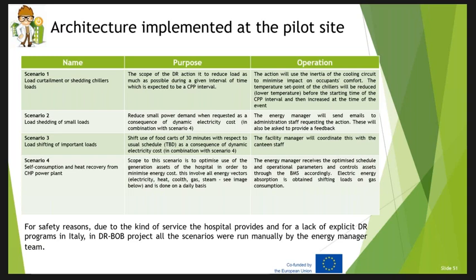We involve people from the technical department of the hospital, like maintenance, who run the scenarios, changing the settings on the BEMS and also locally on the machines, for example, chillers. We implemented four different scenarios for the project. The first one is the control of the electrical chillers. We lower their capacity during demand response events, and we use the inertia of the water in the hydronic circuit, so we use that water as a thermal storage.